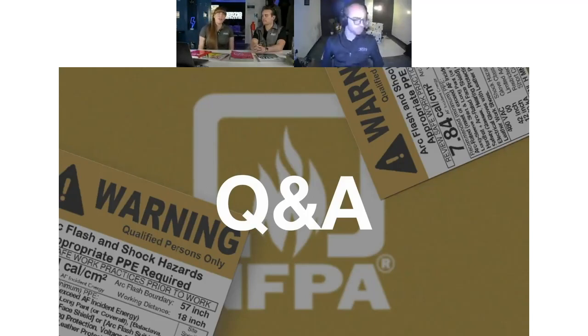That's a good question. Whenever you're talking about analyzing electrical systems, infrared is a hot button topic and very important to do, but that's not quite what we're talking about here. We're talking about a system study that boils down to an engineering calculation. Infrared scans are a little different, they fall under the new 70B for sure, considered an electrical inspection test, typically a non-contact test. If you refer to Chapter 7 of NFPA 70B, it covers the infrared portion and requirements for that type of testing, specifically section 7.2.1.1.